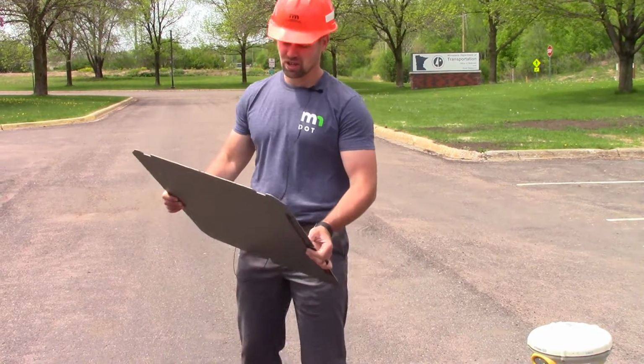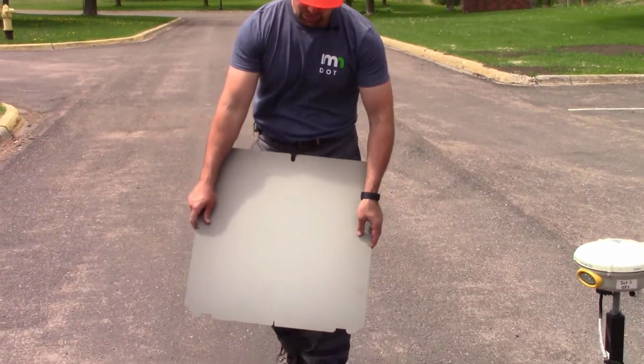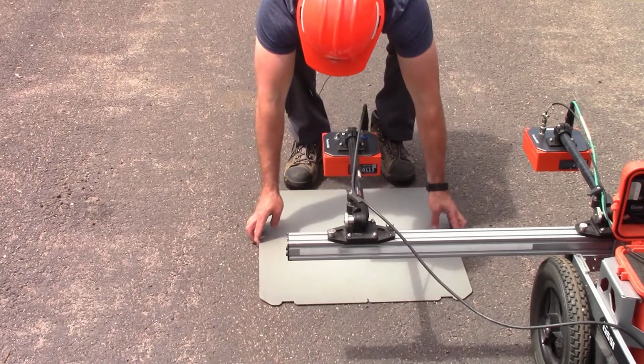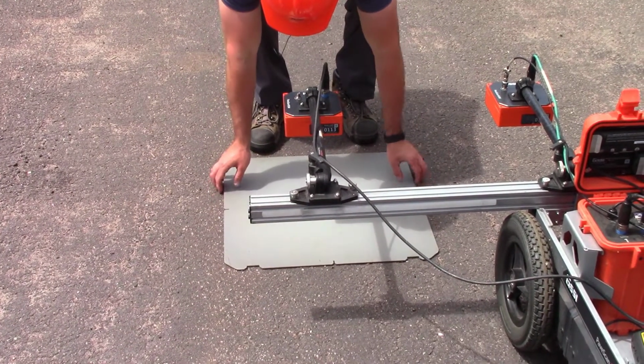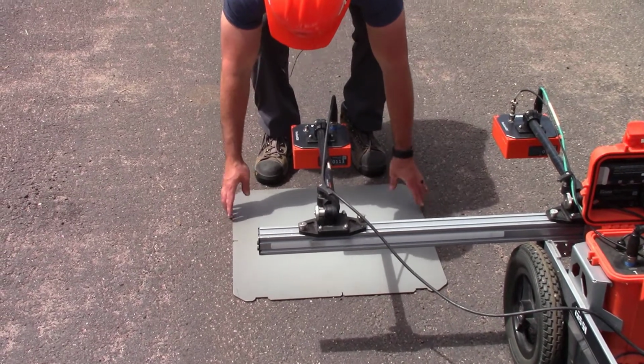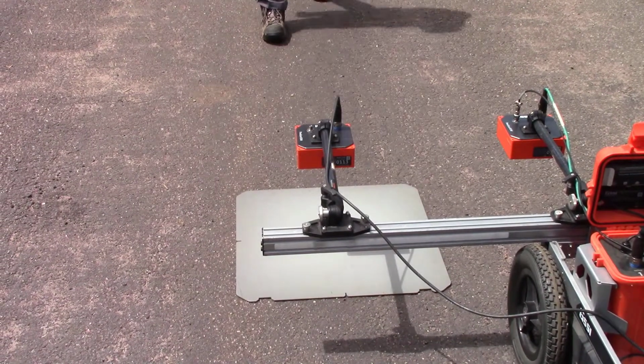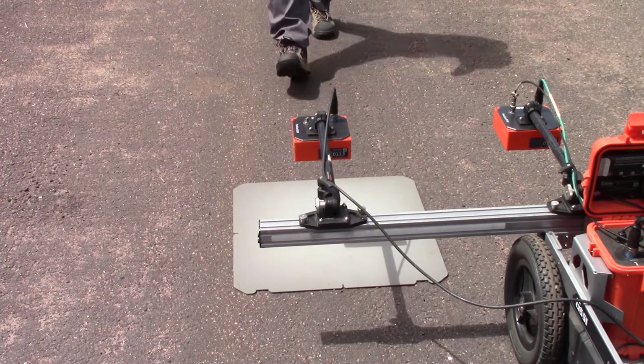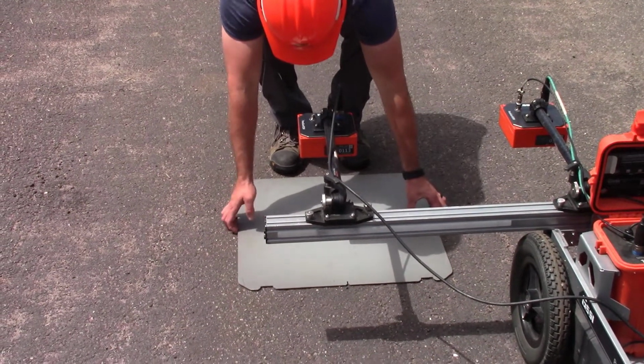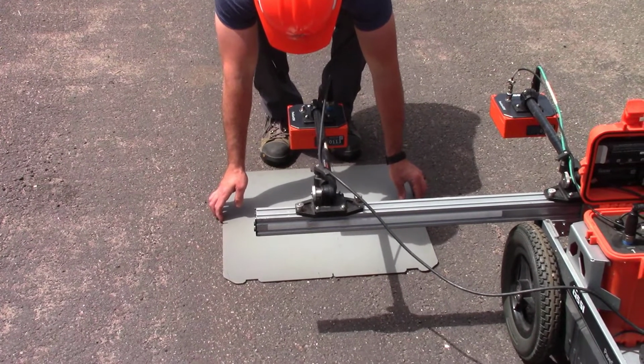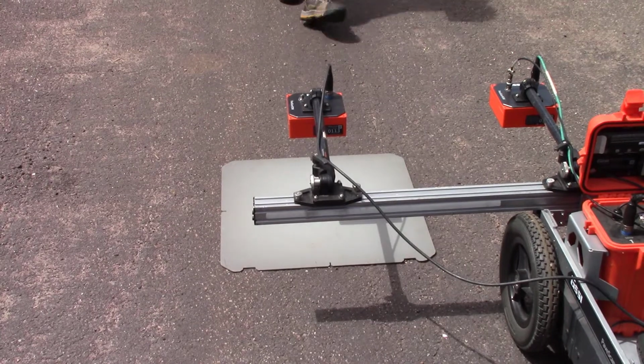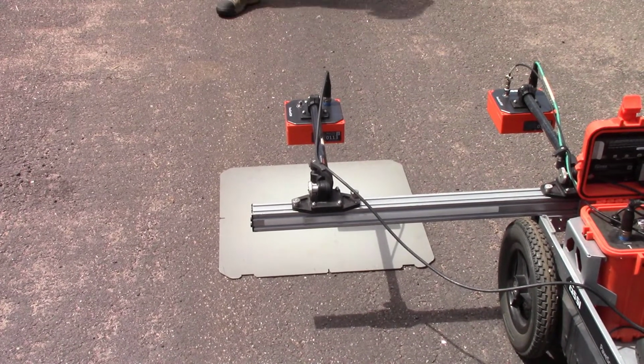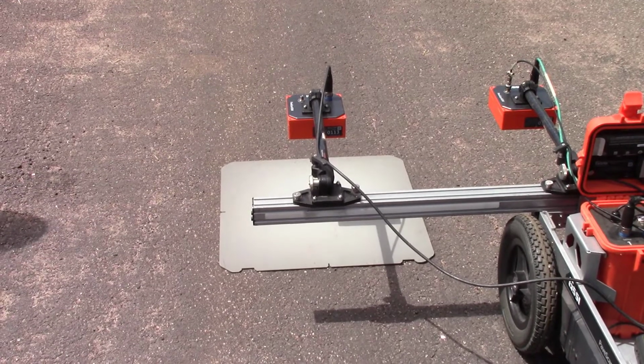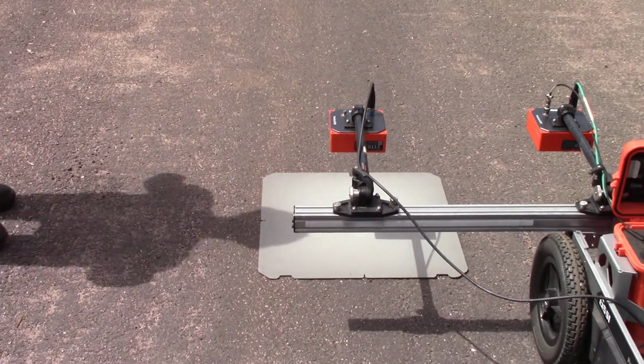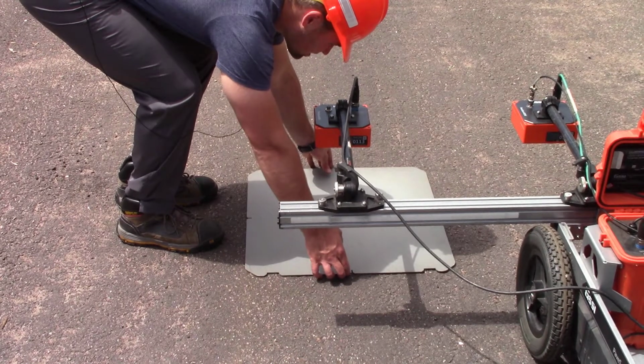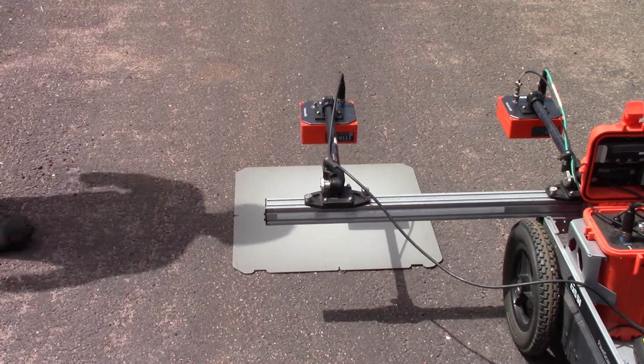We're now ready to do our metal plate calibration. To accomplish this, we're going to place our metal plate such that it's centered below our left sensor, since that was the one highlighted in green. It's best to take a step back and look at your centering job and make any necessary adjustments from there. And I like to do this in both directions just to make sure that your plate is relatively centered when you're accomplishing this measurement.